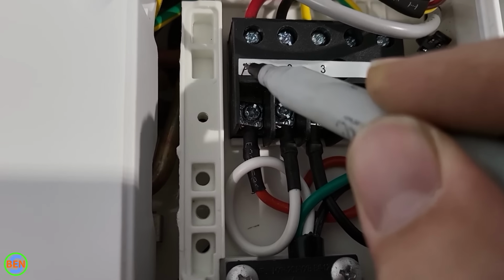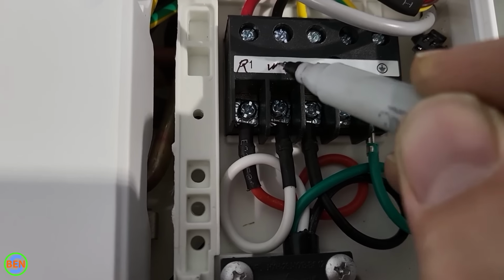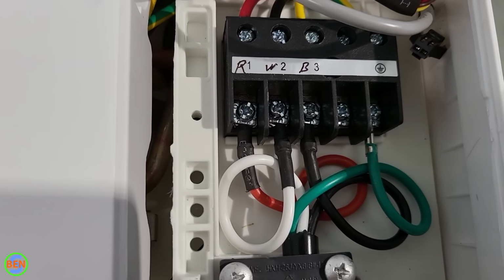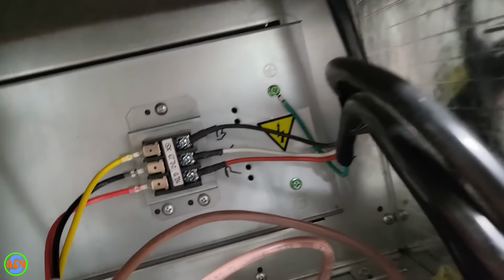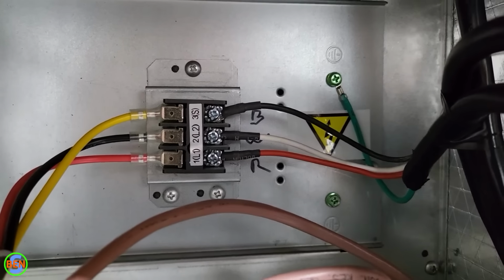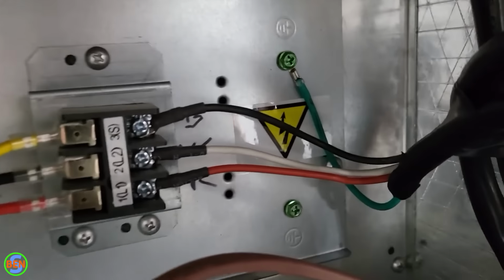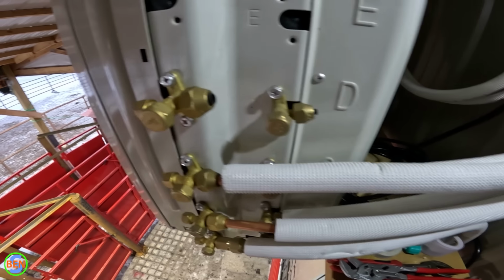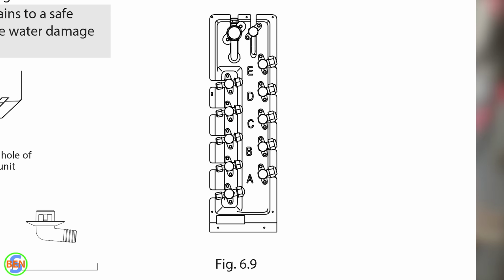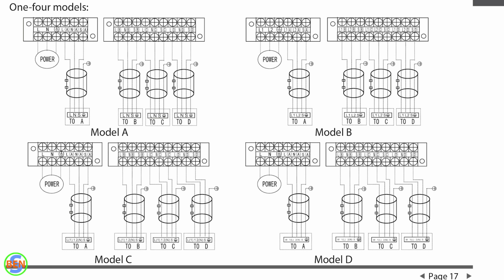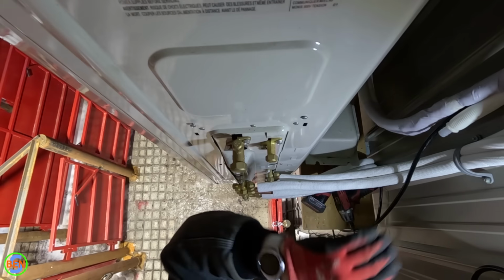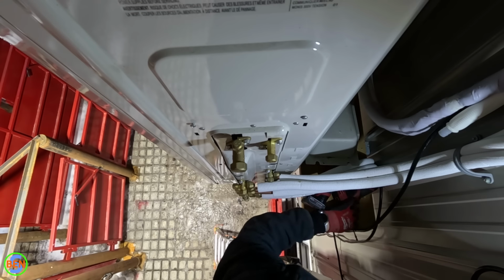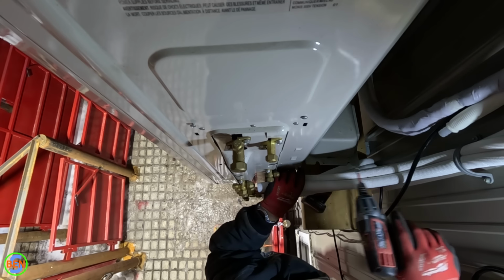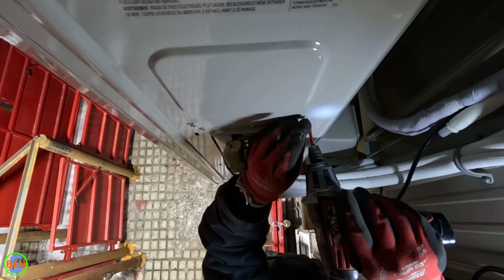Those 4-conductor cables are really straightforward to hook up both in the outdoor unit and the indoor unit, just because they are numbered, and you just have to line up the colors, make sure that they're hooked up the same on the inside and the outside, and you should be good to go. Now, each line set is marked either A, B, C, D, and so on and so forth, and the sets of wires on the outside unit are marked similarly, where they're marked A, B, C, or D, and so you just have to make sure that the line set and wires corresponding to that line set hook to the correct spot for that particular indoor unit.